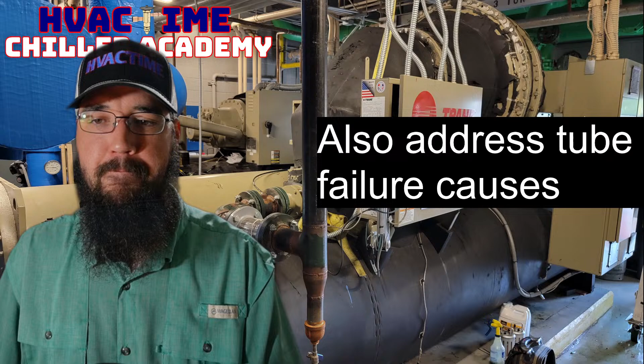So, tube failures. What a tube failure means in the first place is that we've got a failure, whether it be in our evaporator or, if we have a water-cooled condenser, either way. Being a chiller, you're going to have a hydronic evaporator. That is the baseline definition of what makes a chiller to begin with. So you've got a set of tubes in there on some level. And then you could have a water-cooled condenser as another way of saying that. So there are a few ways to go about why the tube has failed.